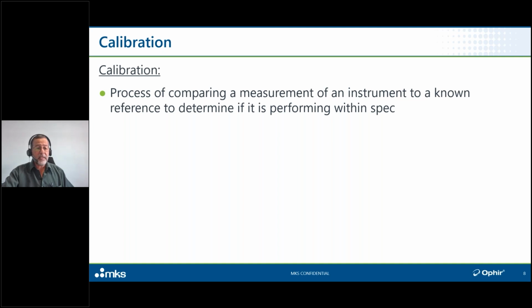Calibration is the process of comparing a measurement from the instrument being calibrated to a known reference, let's say a NIST-provided reference sensor, to determine if it's performing within spec. It would probably be more correct if I said to determine how close, well, if it's performing within spec, how far it is from the reference, from the absolute truth. It can include an additional step of then adjusting the instrument being calibrated so that it actually reads as close as possible to that reference. But strictly speaking, it doesn't have to include that adjustment. Using the definitions of the ISO standards, it doesn't actually include the adjustments.